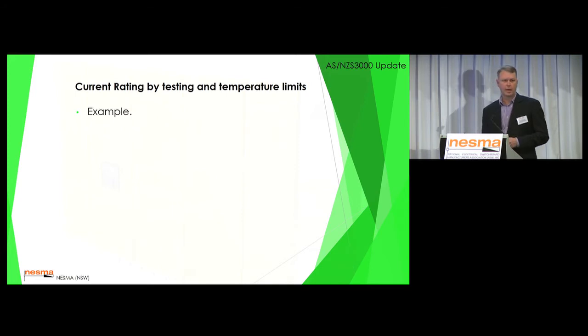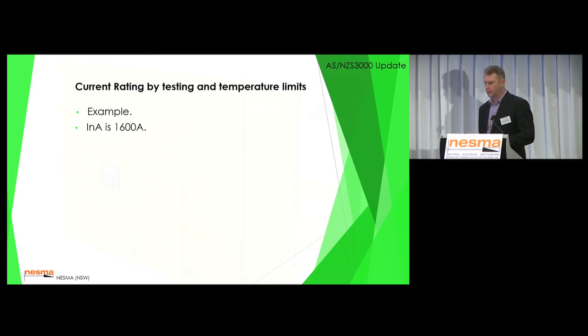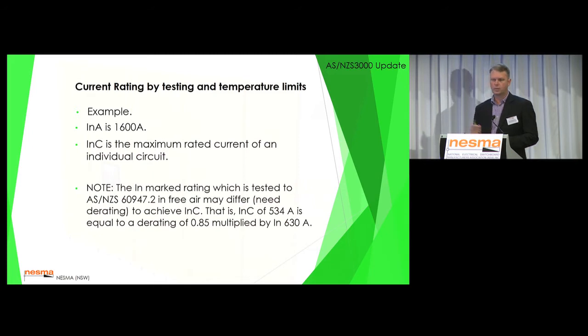So we've got an example in the back now with Appendix K. If we assume that INA, there's 1600 amp switchboard, INC is the maximum rated current of an individual circuit. Now we must accept that the IN rating of an individual circuit breaker, let's take a 630 amp circuit breaker, may not be 630 amps when it's put inside a switchboard. We've got a derating factor depending on air movement, copper connection onto the breaker, the ability for that to dissipate heat. So in this situation, this calculation, we've got an INC of 534 amps, which is a derating of 0.85.